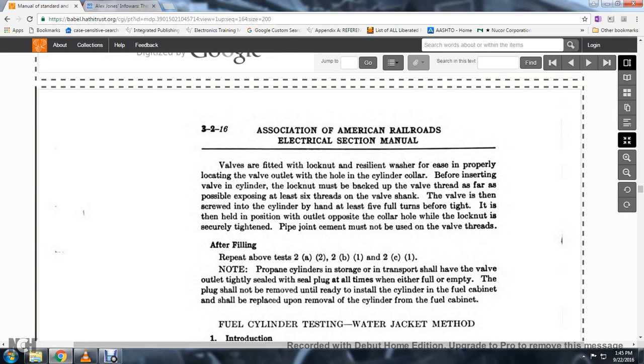Valves are fitted with a locknut and resilient washer for properly locating the valve outlet with a hole in the cylinder collar. Before inserting the valve in the cylinder, the locknut must be backed up on the valve threads as far as possible, exposing at least six threads on the valve shank. The valve is then screwed into the cylinder by hand at least five full turns before tight, then held in position with the outlet opposite the collar hole while the locknut is securely tightened. Pipe joint cement must not be used on the valve threads.